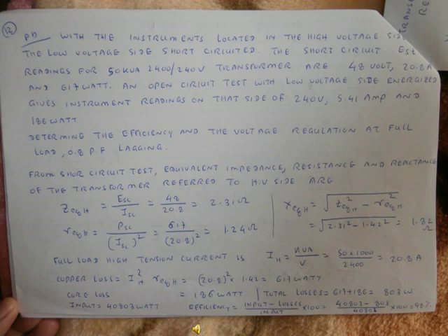And also, we use the open circuit test. The open circuit test is applied on the low voltage side. In this case, the applied voltage is 240 volt, the current is 5.41 ampere, and the power consumption is 186 watt. So for this problem, we have to determine the efficiency and the voltage regulation, and the full load is at 0.8 power factor lagging.